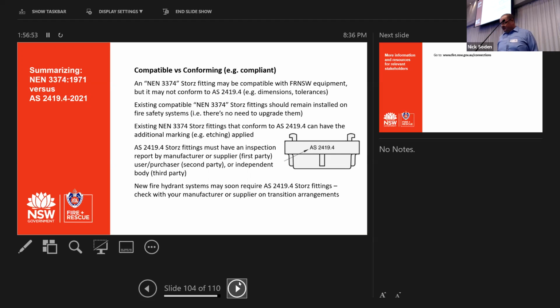New fire hydrant systems may soon require AS 2419 Part 4 Storz fittings. So at the earliest, and there's going to be a transition period, at the earliest, if it does get referenced in Part 1, it won't get referenced by the building code till 2022. So you won't necessarily need to see any of these until mid next year. But we are going to be communicating with the suppliers and letting them know and start that transition period happening sooner rather than later.